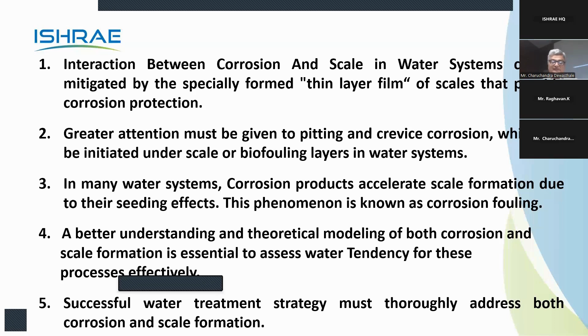Better understanding and theoretical modeling of both corrosion and scale formation is essential to assess the water's tendency for this process effectively. There are experts available in the market, so whatever you do should be done in consultation with them. A successful water treatment strategy must thoroughly address both corrosion and scale formation, and the issue is not only corrosion and scale but also biological formation and fouling issues.